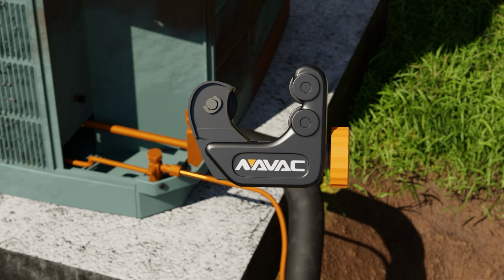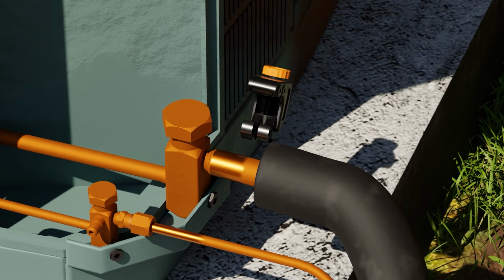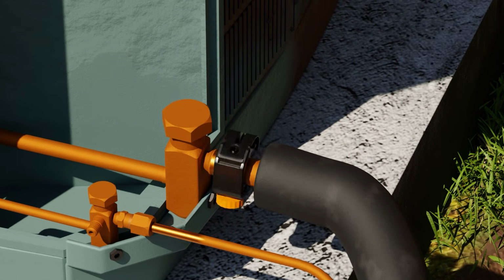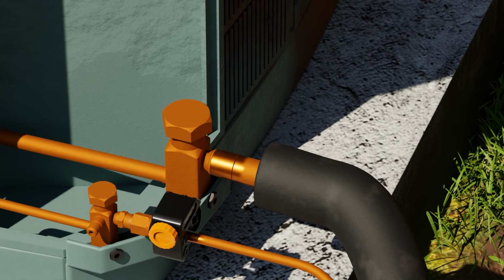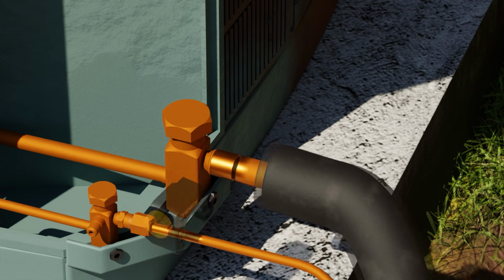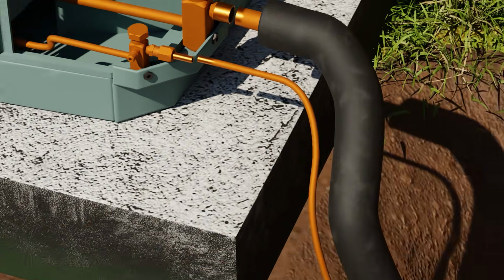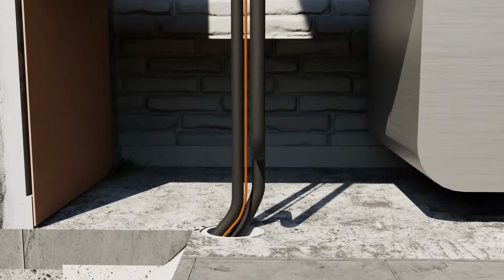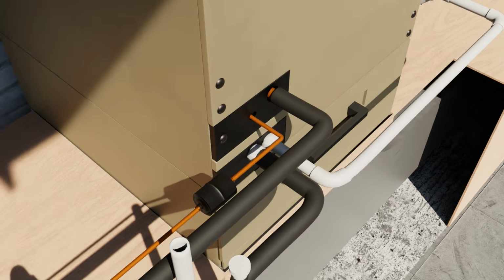Regardless of your process, you need to cut your copper at the inside and outside. Here we show cleaning the copper before you cut it with a proper tubing cutter. This is one of the best practices because it ensures that you don't have to clean it when it's already been cut, which can result in pieces of copper and contaminants falling into the lines.